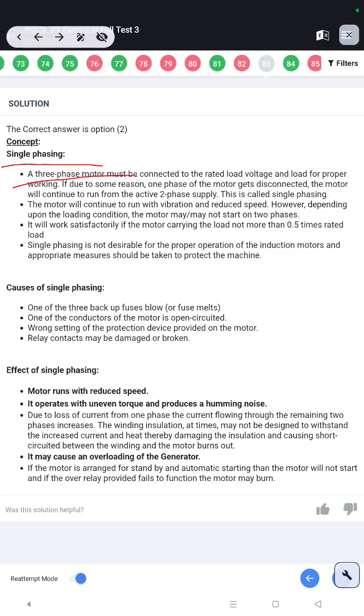Single phasing. A 3-phase motor must be connected to the rated load voltage and load for proper working. If due to some reason one phase of the motor gets disconnected, the motor will continue to run from the active two-phase supply. This is called single phasing. The motor will continue to run with vibration and reduced speed. However, depending upon the loading condition, the motor may not start on two phases.